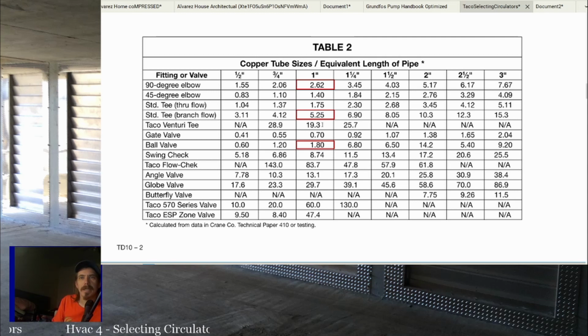You'll usually see most of your ball valves and stuff, right? You'll know how many ball valves you'll have in there, and you can guess how many elbows to get to that pipe. How did they run it? Well, they had to have run up to the first floor and the second floor, in the ceiling above the first, right? Based on where the pipe runs, they probably went around in this loop and then came back down. You can take a pretty good guess at how many 90s are in there and then add a few to be safe, and you can estimate what your head loss is going to be in the system.